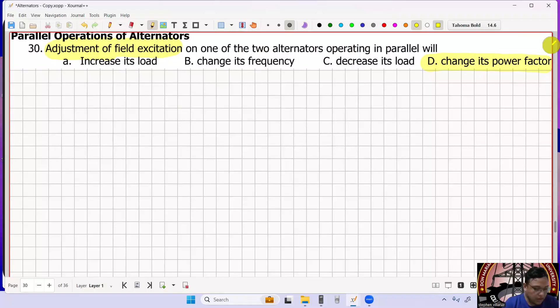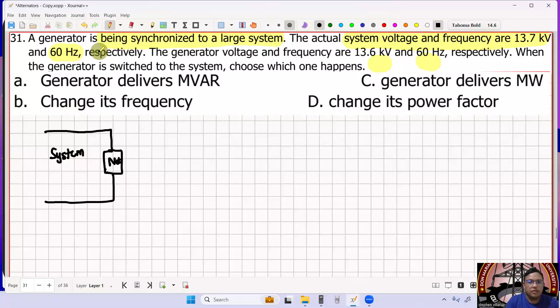Number 31: we have a generator being synchronized to a large system. The actual system voltage and frequency are 13.7 kV and 60 Hertz, respectively. The generator voltage and frequency are 13.6 kV and 60 Hertz, respectively. So we have a system network at 13.7 kilovolts and 60 Hertz. Now we're adding a generator rated 13.6 kV and 60 Hertz.